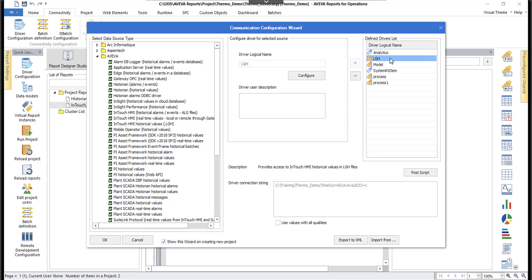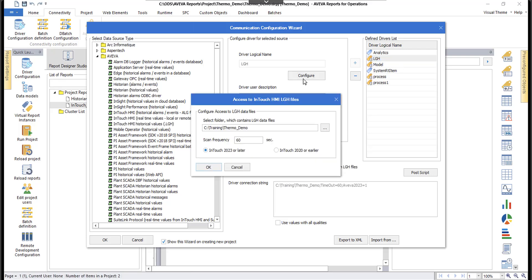I'll show you the LGH database configuration quickly. It asks you to configure access to the LGH data files — you select the folder where those LGH files are located. In my case it's in the same application directory. You can also change the scan frequency and choose the InTouch version: 2023 and later, or 2020 and earlier. This is already configured and tested.